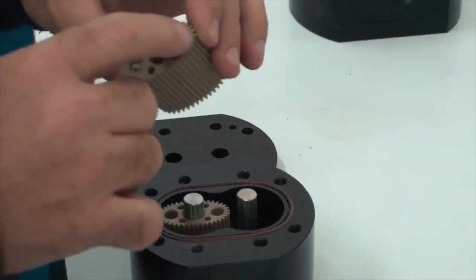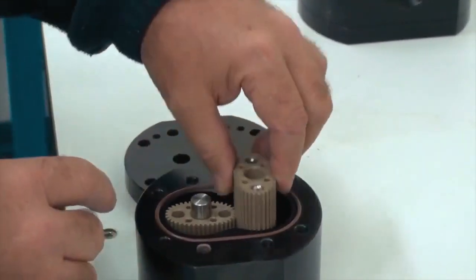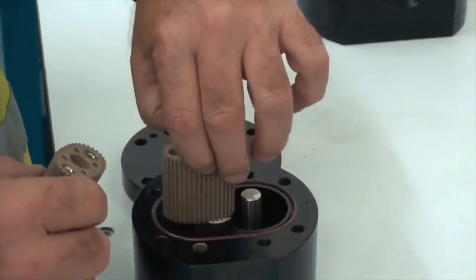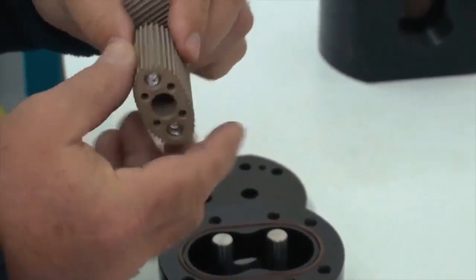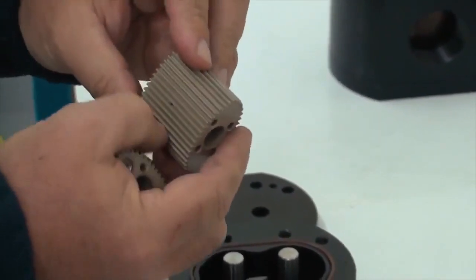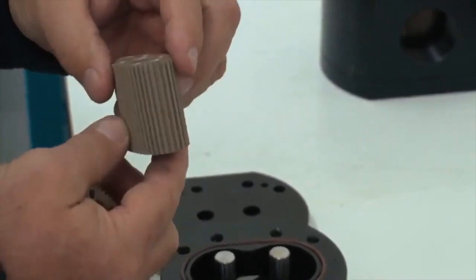That's our active rotor with the magnets in it and that goes with the magnets down. We'll remove our two rotors. We need to physically inspect them and make sure that there's no damage at all to them, no missing teeth, nothing jammed in the actual rotors themselves. They all look okay.